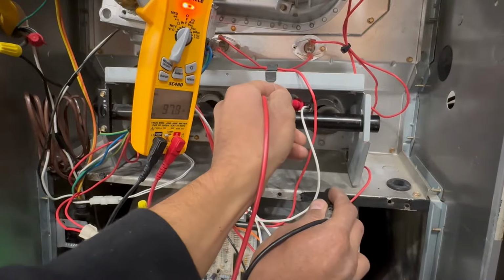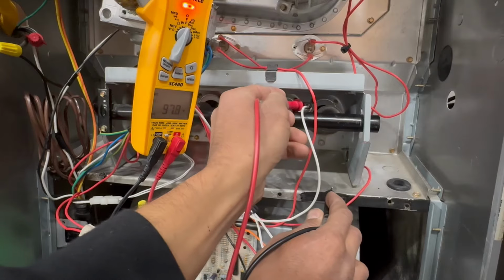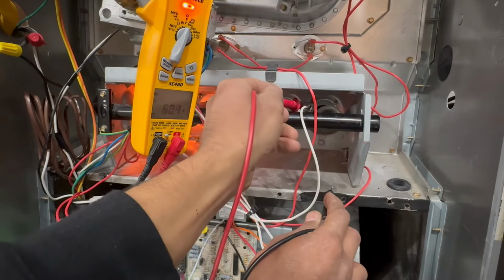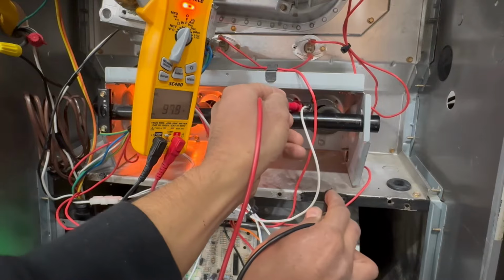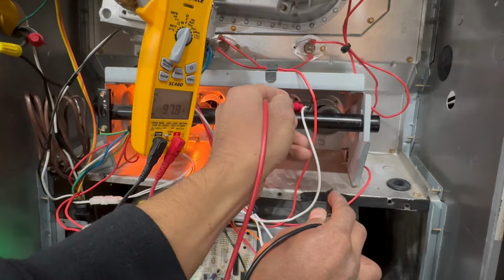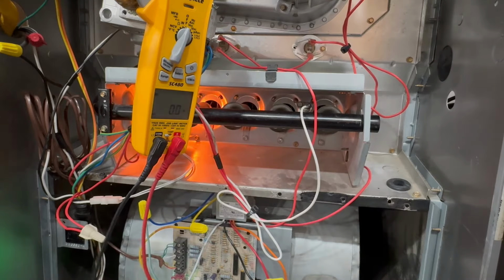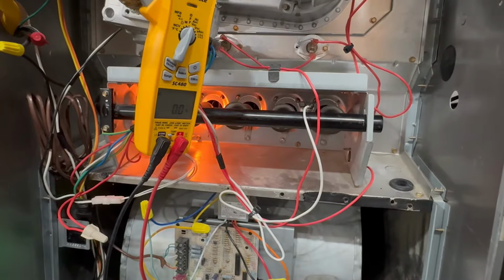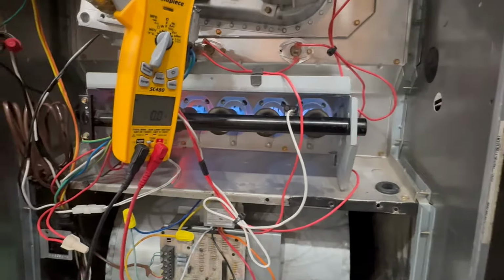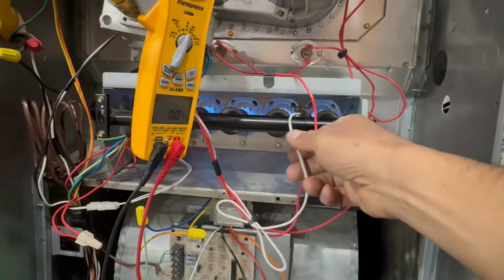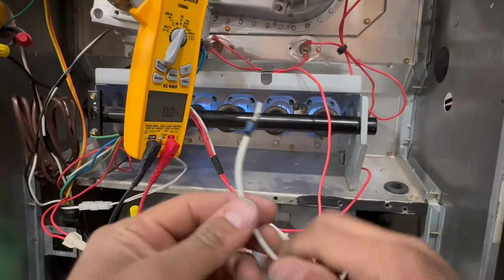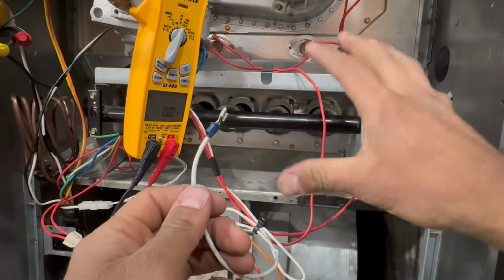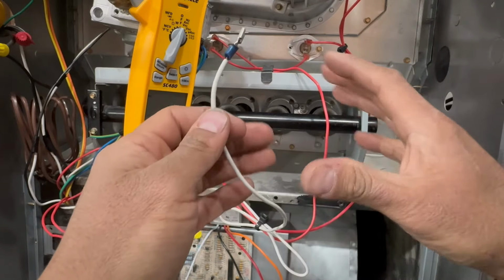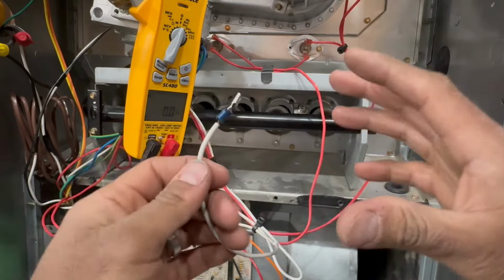I'm going to put it to metal. You see, I'm getting 97 volts, so 80 to 100 volts. You can touch the flame sensor and then anywhere on ground, 80 to 100 volts. So that's good. There's voltage present. You want to make sure the board is sending voltage to the flame sensor. A good indication of a bad flame sensor is that it's dirty. If it's dirty, you will get flames for a couple of seconds, and then the flames will turn off. That will prompt you to look at the flame sensor to see if it's dirty.